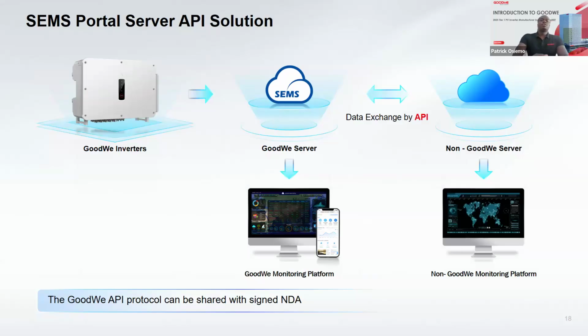And we've had a number of EPCs using different third-party monitoring systems. The meaning of third party is that EPCs would like to use a single monitoring system, even if they're doing different inverters. So with GoodWe, our monitoring portal, which is called SEMS, can be integrated through API to your third-party monitoring systems. So even though you're monitoring using your own monitoring system, our inverters can still connect to our monitoring system, and the data on both portals will be identical. So we can troubleshoot using our system. You can also see troubleshooting and monitoring using your own monitoring system. So that is the API integration.